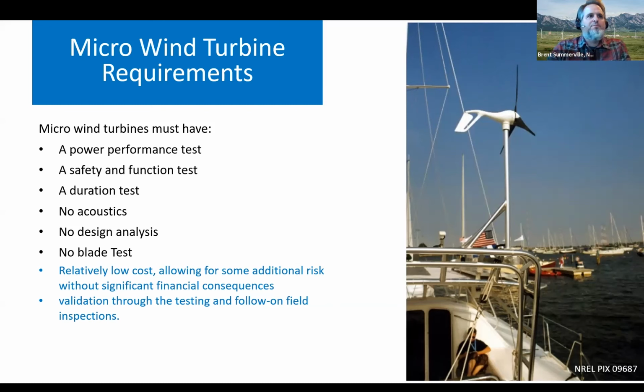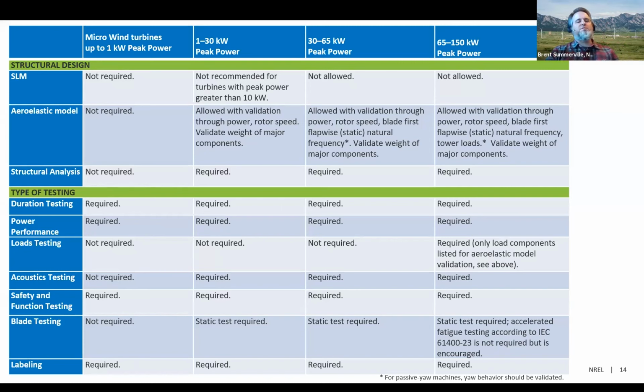Yeah, if that's okay. There's a table at the end of the standard that breaks down slightly different requirements in 4 subcategories: micro wind, 1 to 30 kilowatts, 30 to 65, and 65 to 150. So we've talked about micro wind in terms of not requiring a structural analysis and then some testing. For 30 kilowatt machines and down, you can use the simplified load method for this category, but it's not recommended for turbines greater than 10 kilowatts.